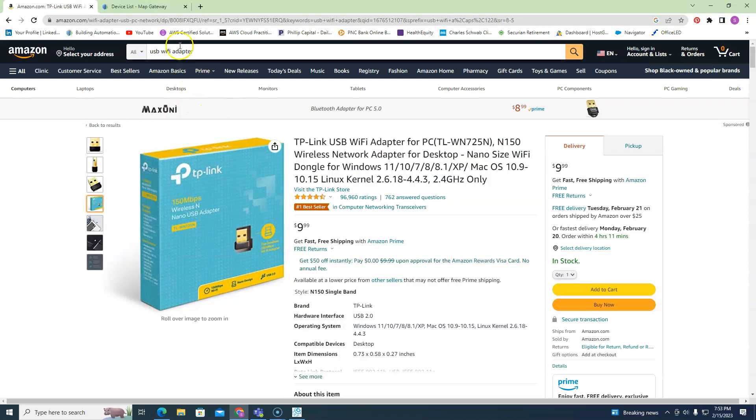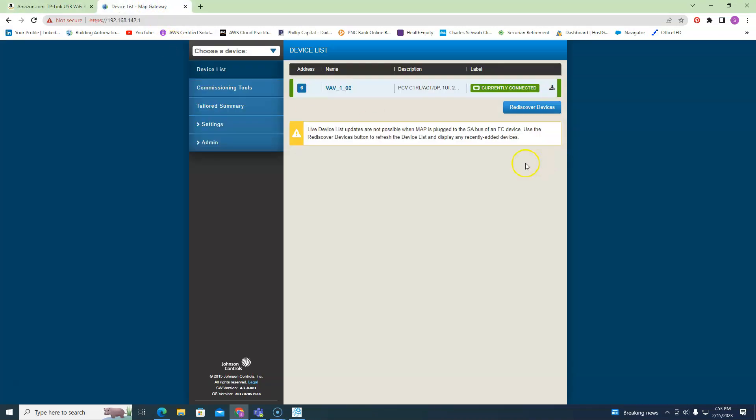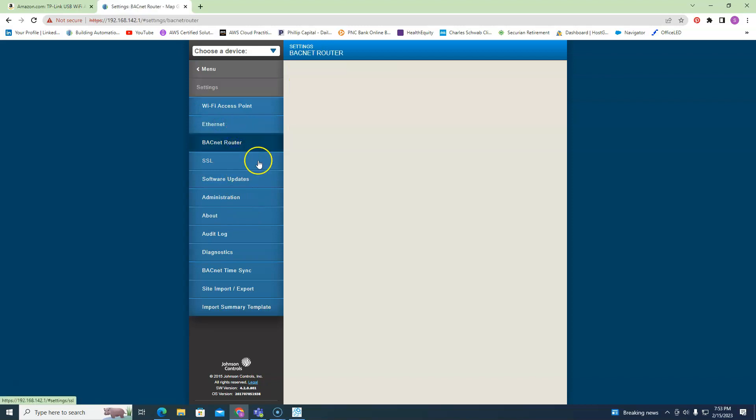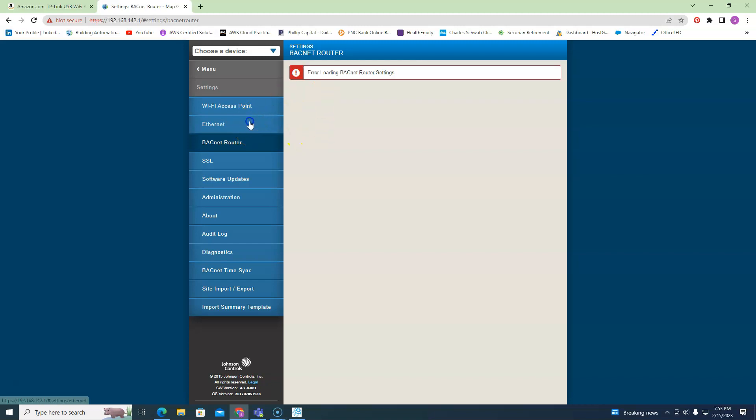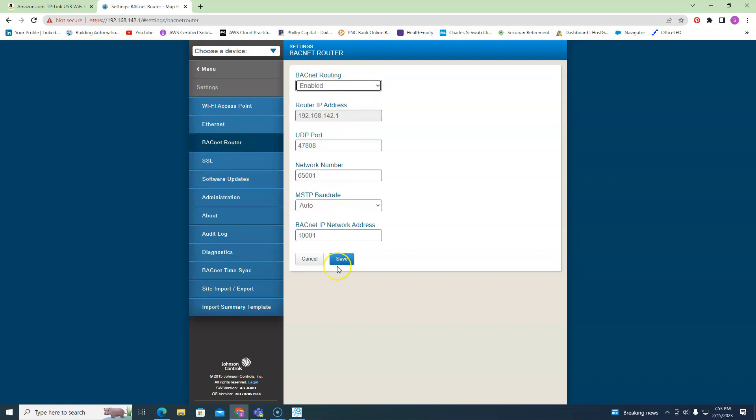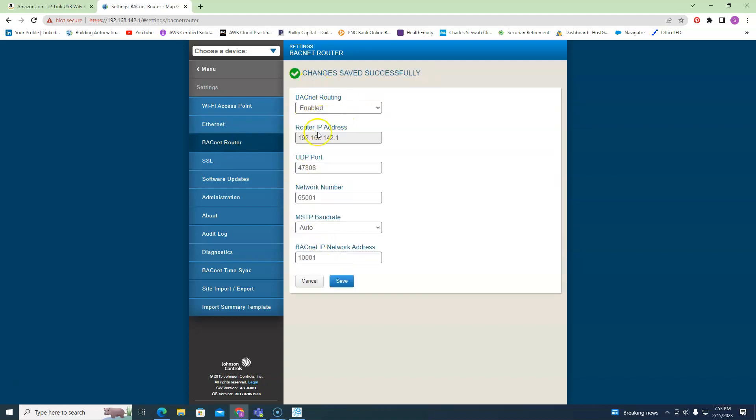Second thing is, go into your MAP Gateway settings, go into Settings and go into BACnet Router, and make sure your routing is enabled. If this says disabled, then that's the reason why it's not working. So go in there and make it enabled, save it, make sure it's enabled.